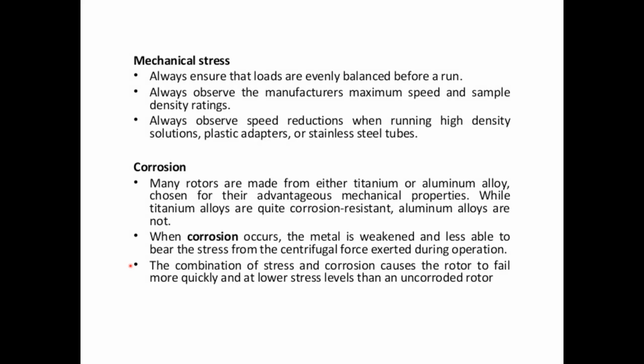Be sure that you know what is the maximal speed you can go with a centrifuge and with the tubes that are supplied, because what happens is when you take the wrong tubes that are not designed to stand at centrifugation speed of 100,000 G, they will collapse and all the liquid will distribute then in the centrifuge.